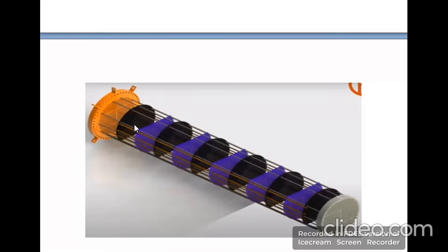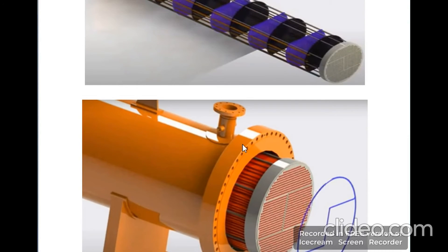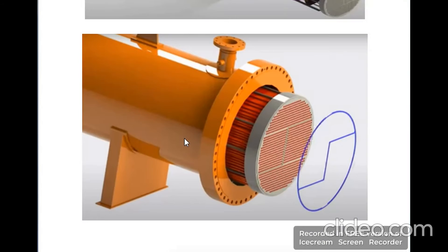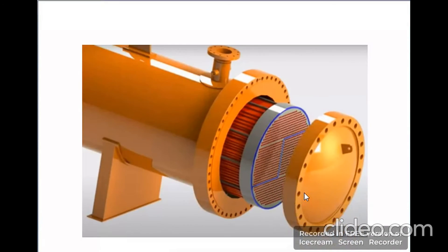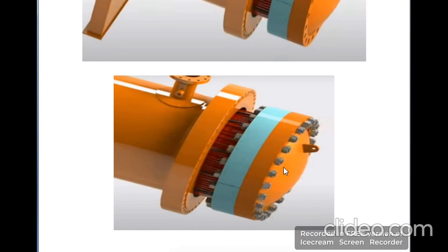The purpose of the baffles is to improve the rate of heat transfer. In the next diagram, all the previous assembly is fitted into a shell. At one end we are preparing the floating head, and a blue circle represents a gasket which is used to avoid leakage. A circular plate in a curved shape fits over both the tubes and the gasket, and once fitted it is bolted but not to the shell — so it is free to move back and forth during high temperature stresses.